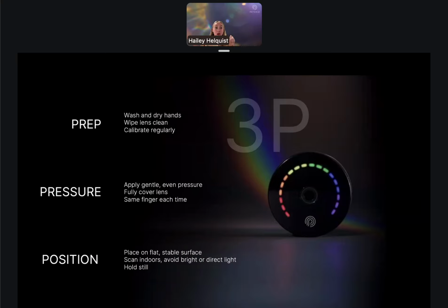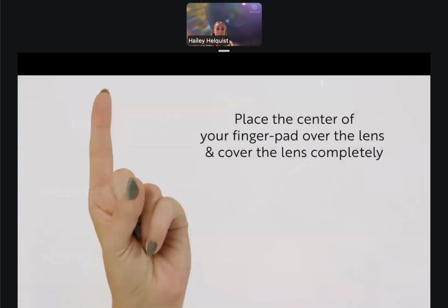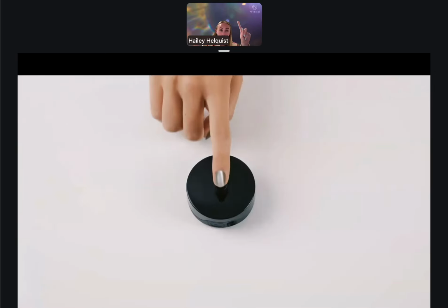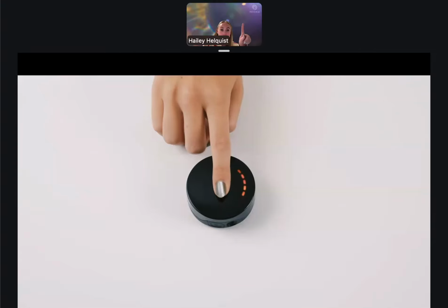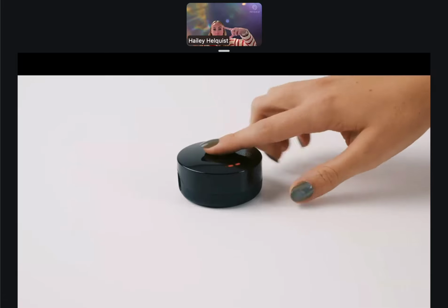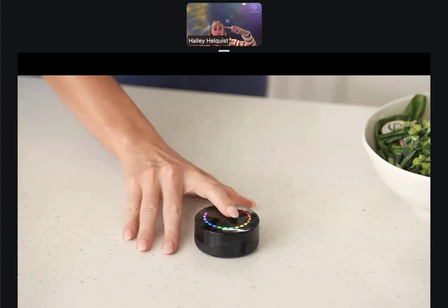So again, prep, pressure, and position, all of these will help lead to more consistent results. So again, like we mentioned, making sure that you're using that center of your index finger as you are scanning. Making sure that you're not scanning on the tip, but that it's staying flat on the finger pad.